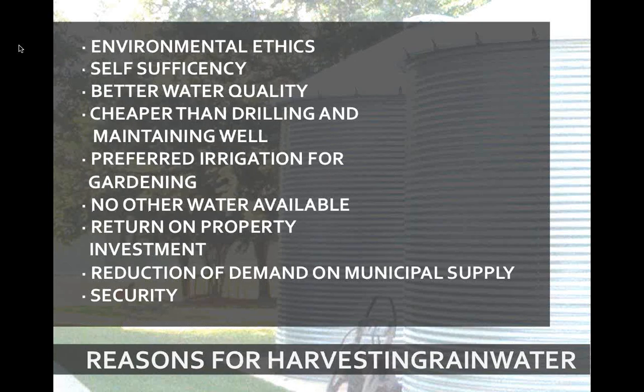One thing I'd add to the list of reasons to harvest rainwater is volume reduction for stormwater mitigation. When using rainwater harvesting as a stormwater mitigation tool, you need to have a water-use regime so the tank is not left full — you really need 50% or more of the tank volume available for storm surge. If the tank is full most of the time, it's negligible as a stormwater technique.